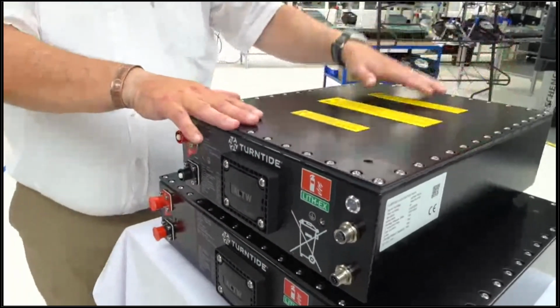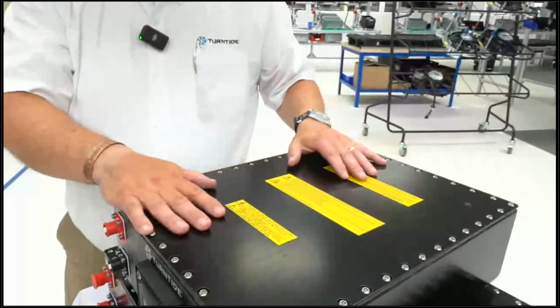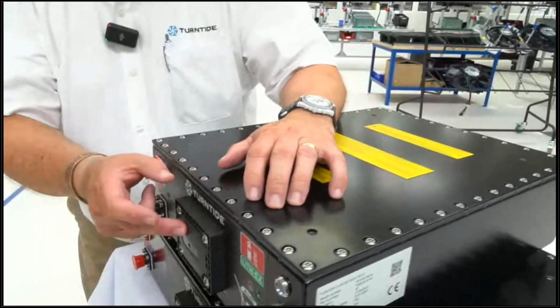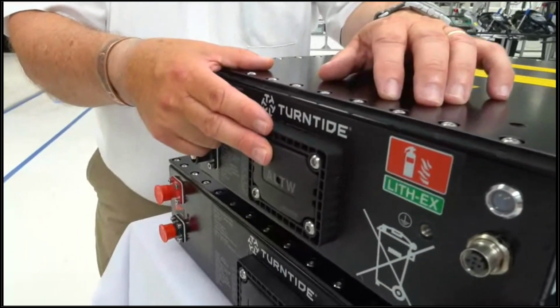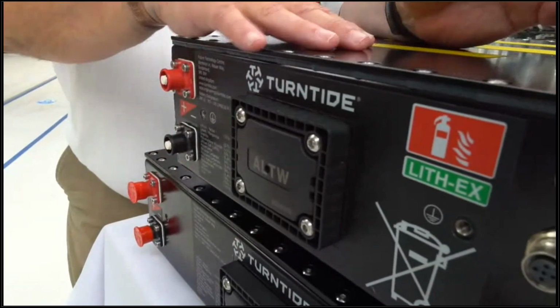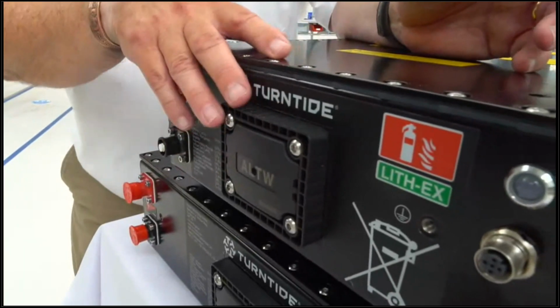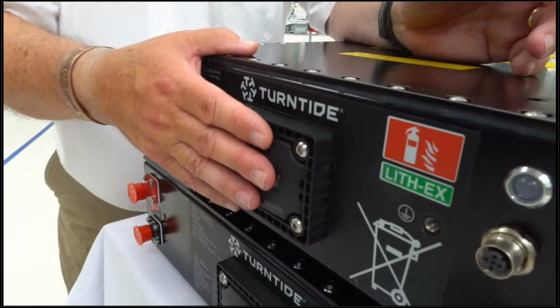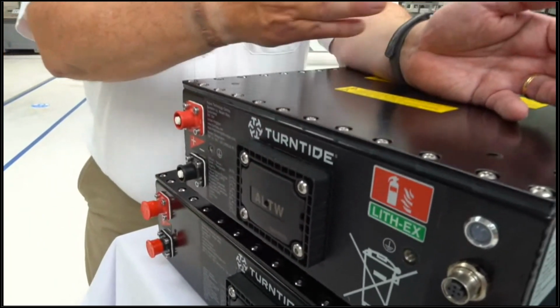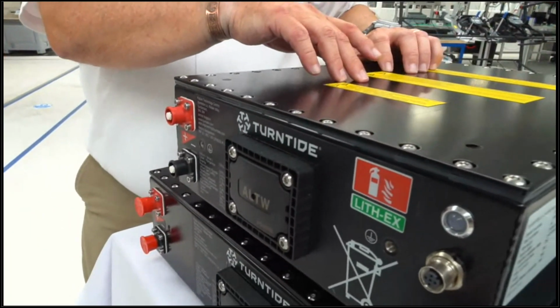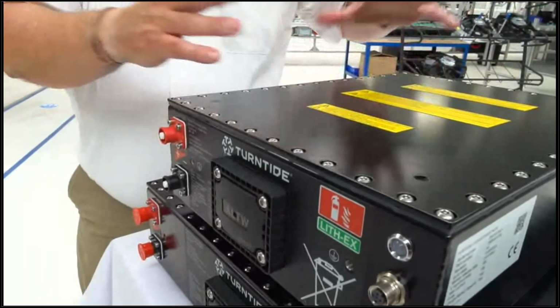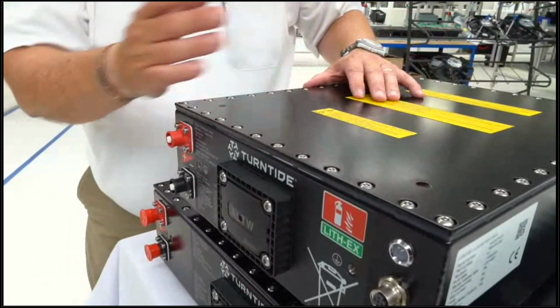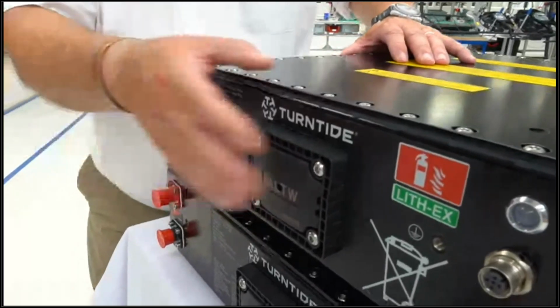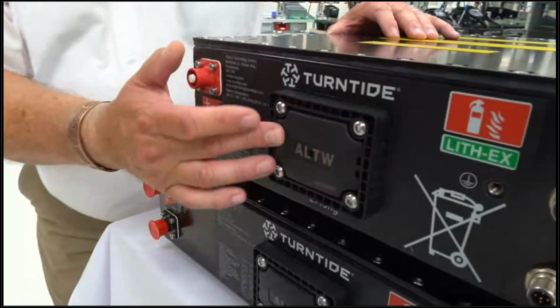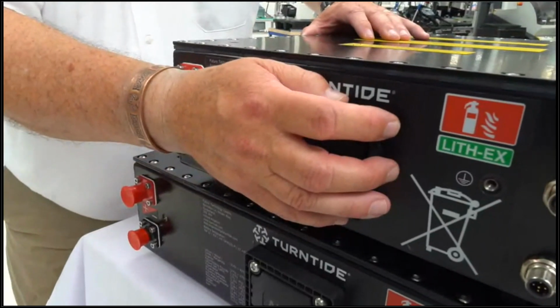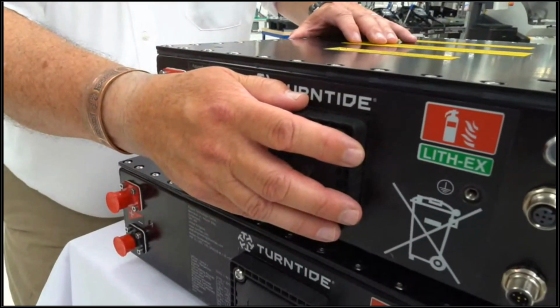One of the things that helps us pass the stringent testing on thermal propagation is a blowout valve we've fitted here. As well as acting as a pressure relief and equalization valve, this will activate once at a certain pressure. So if there's a thermal event within the battery pack and pressure and temperature build up, this will blow out at a safe pressure, and it's all controlled so we know which direction it comes from.